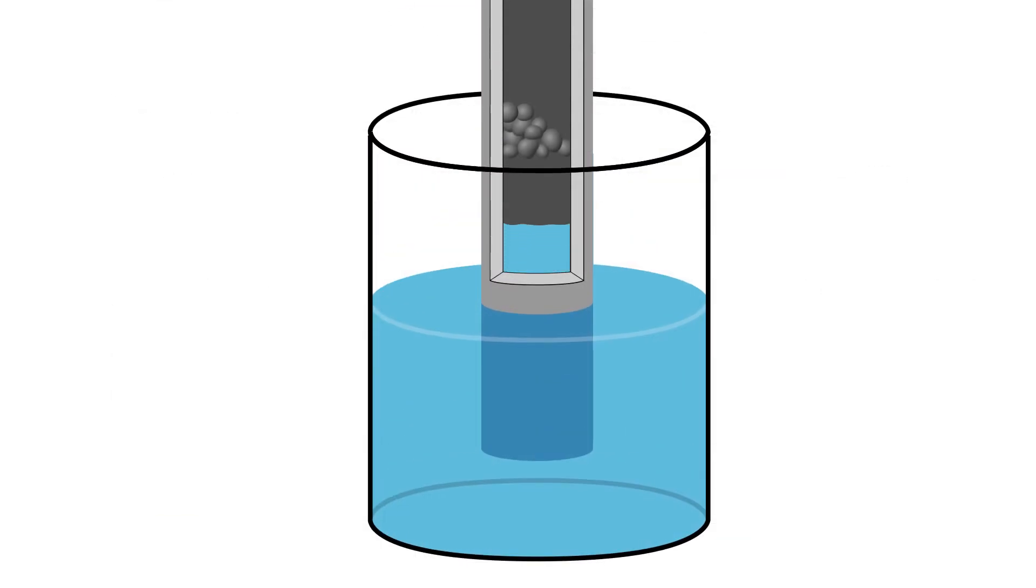The probe may be clogged, preventing any reagent uptake, or the probe may be adjusted to the wrong height, hindering it from taking up the amount of reagent needed.